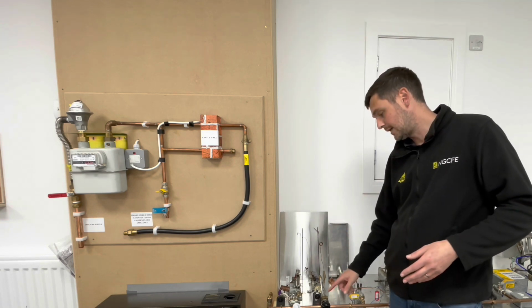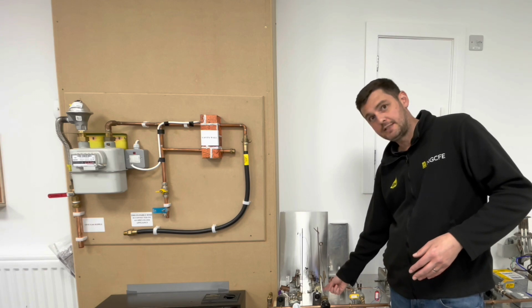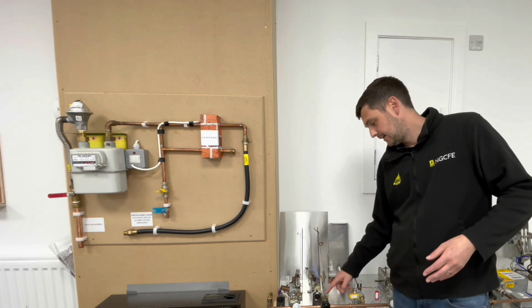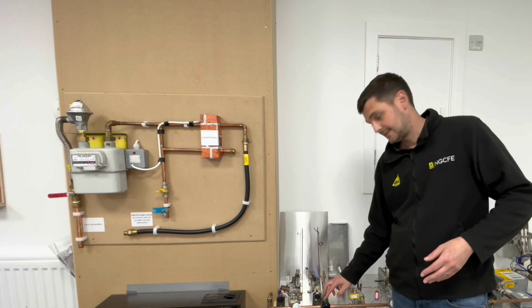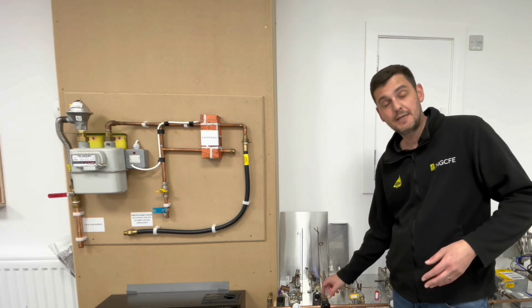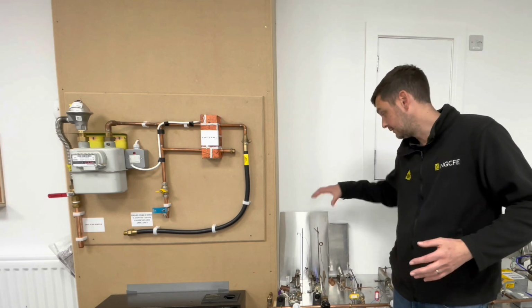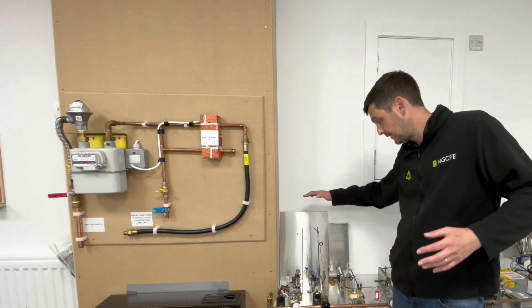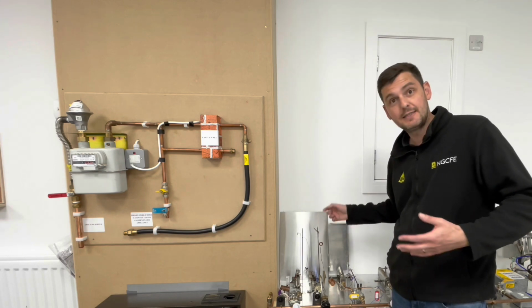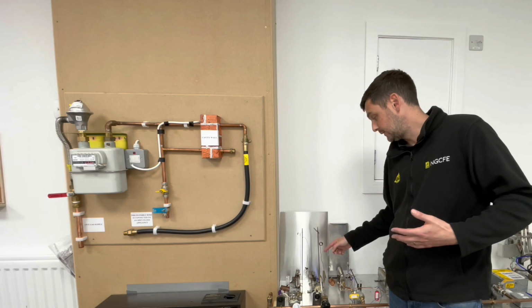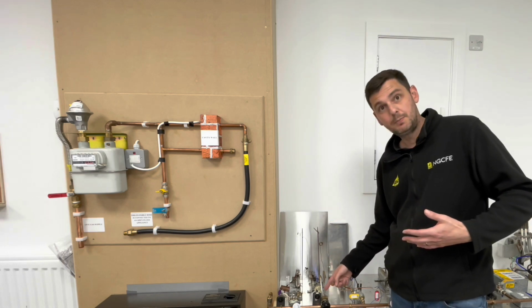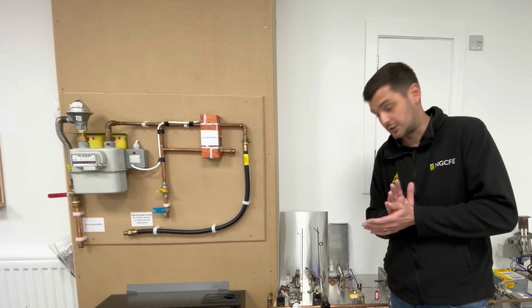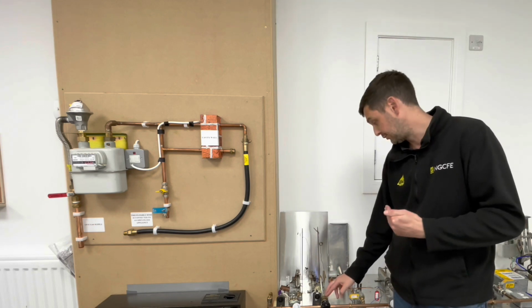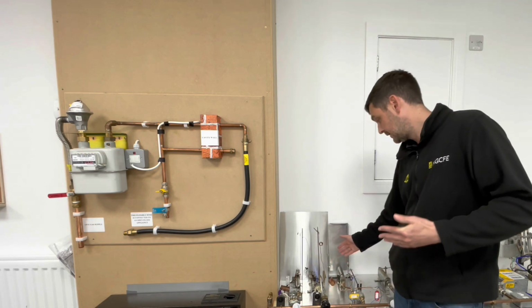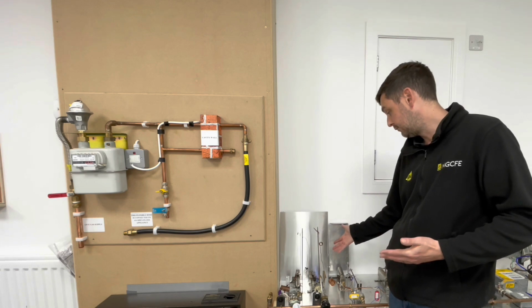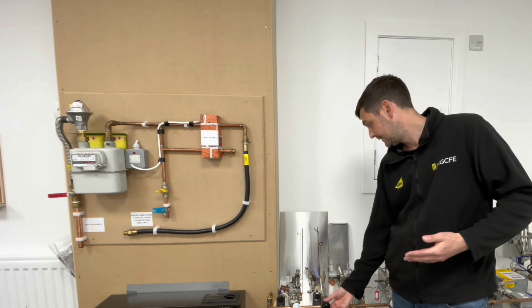It's important to note as well that this is the FSD side, that's the full burner. In here we've got our thermostat. So in here we've got another set of bellows that is fully open until the temperature in our oven gets hot enough for this phial to then heat up. The liquid expansion will carry on through this capillary tube, and then it'll close the set of bellows here, allowing a bypass through, maintaining the flame there. So now we've got a full rate through our flame, through to our burner.